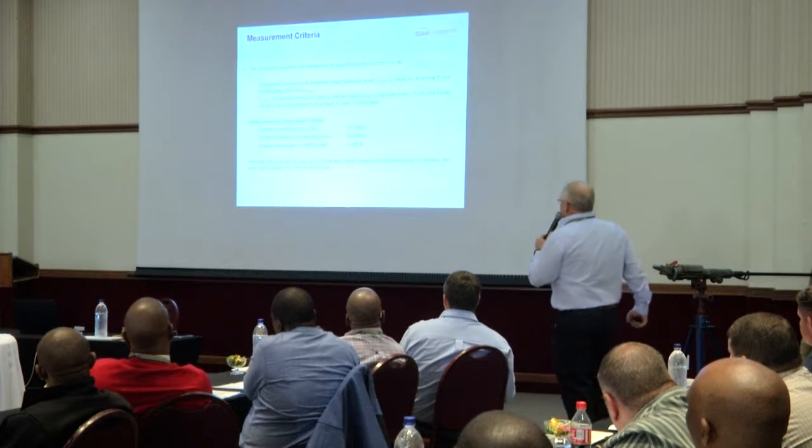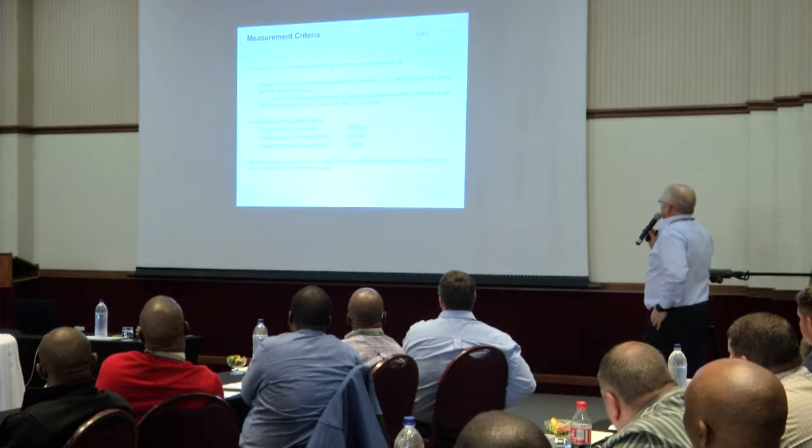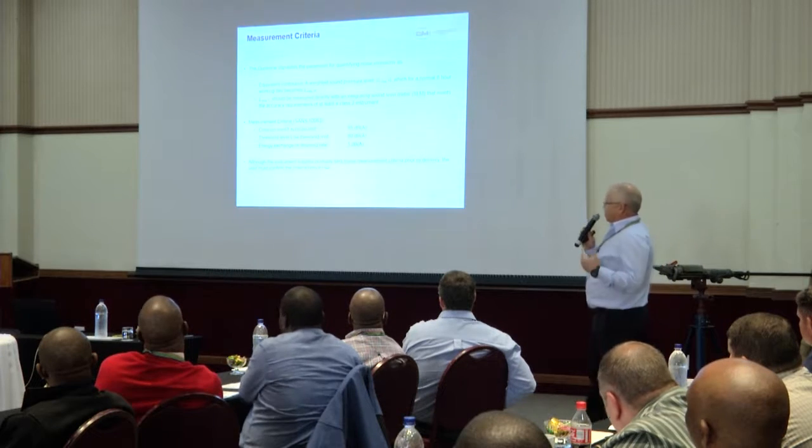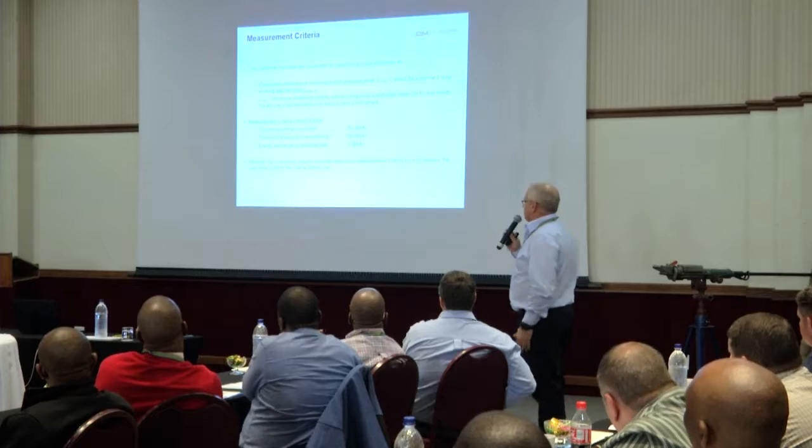All right, so what is the measurement criteria? The guideline stipulates the parameter for quantifying noise emissions as equivalent continuous A-weighted sound pressure level, which for a normal 8-hour work shift becomes the equivalent noise level for 8 hours. It should be measured directly with an integrating sound level meter that meets the accuracy requirements of at least a class 2.